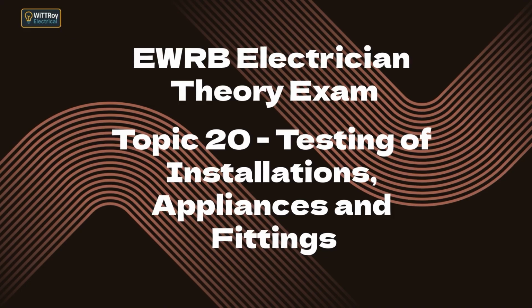Topic 20d. Describe the methods of carrying out the tests specified in AS/NZS 3000 2007, stating the minimum and maximum values, where appropriate, that are acceptable. The methods and acceptable values include continuity of earthing and bonding. Reading must be low resistance, typically less than 1 ohm for bonding conductors. Insulation resistance. Minimum acceptable value, 1 megohm between all conductors. Many electricians aim for much higher values.